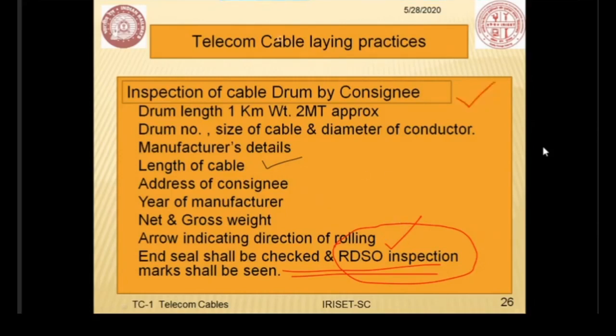Even what I am telling, you may not have all the facilities to verify the end-to-end testing, which is beyond your scope. But you can make the visual inspection. You can test the loop resistance. You can check the insulation resistance. You can check the transmission loss. The test which you can faithfully and comfortably carry out, you should carry out.